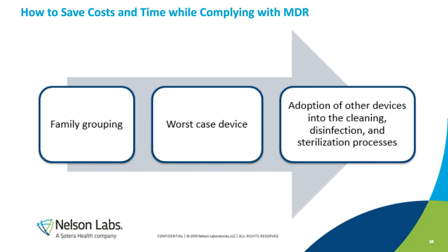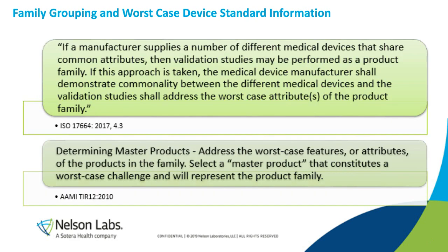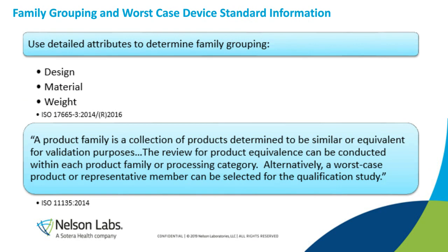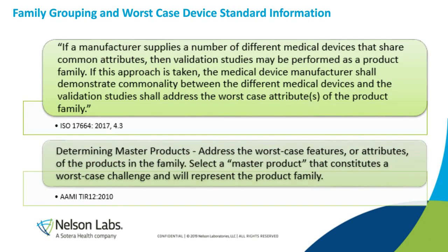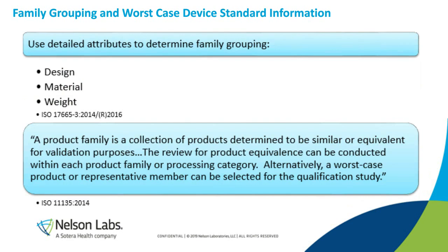All right, now we are getting into the fun part of this presentation and what you've probably all been waiting for. This is how to save cost, time, and comply with medical device regulation. We first need to determine family grouping and worst case device or devices, and then we need to adopt all these other devices into the cleaning, disinfection, and sterilization processes. Now, it's not as easy as it sounds, and it requires extremely robust justifications. I'm missing a slide there, so I'll just talk through it and then we'll move to the next slide.